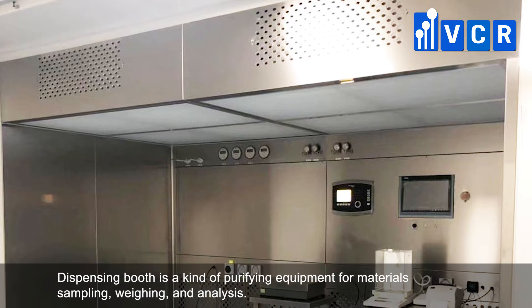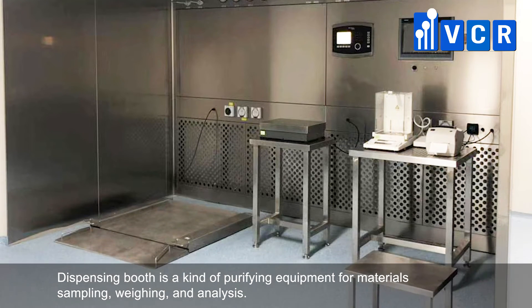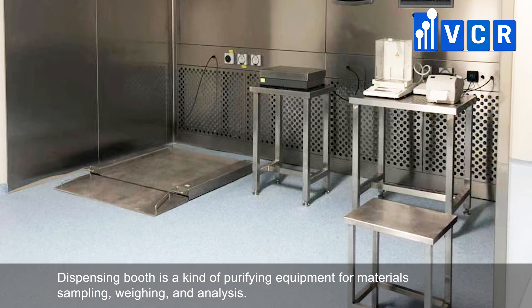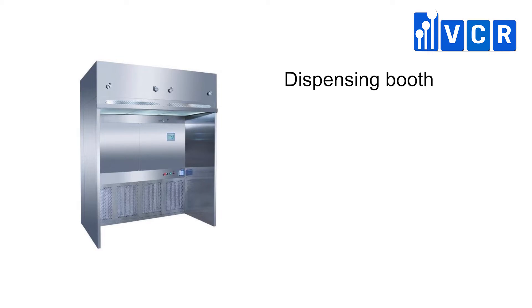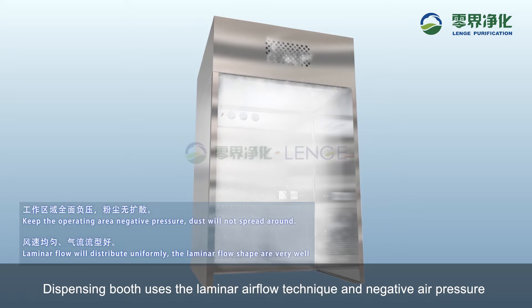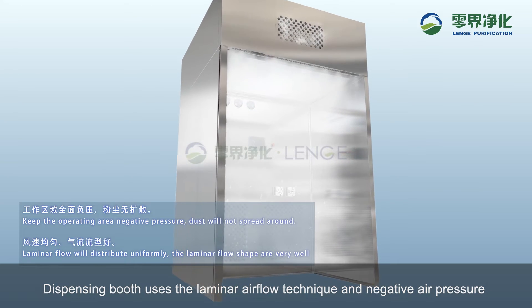A dispensing booth is a kind of purifying equipment for materials sampling, weighing, and analysis. It is also called a sampling booth, a weighing booth, a downflow hood, RLAF (reverse laminar air flow), or a powder containment booth. The dispensing booth uses the laminar airflow technique and negative air pressure.